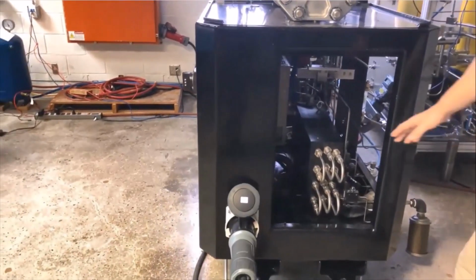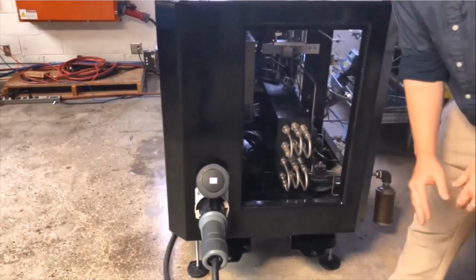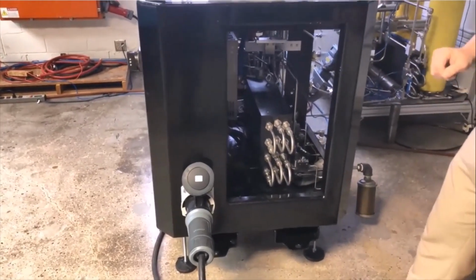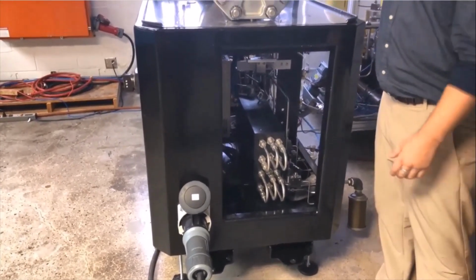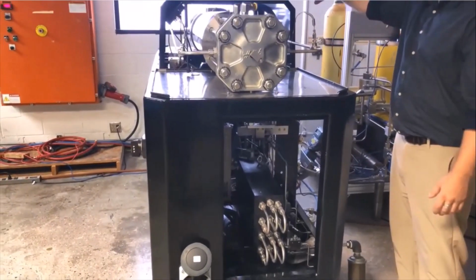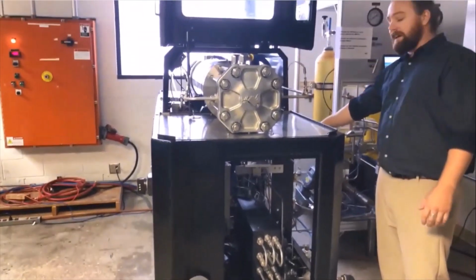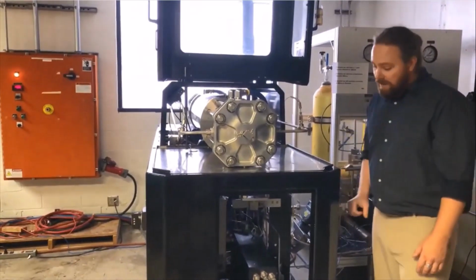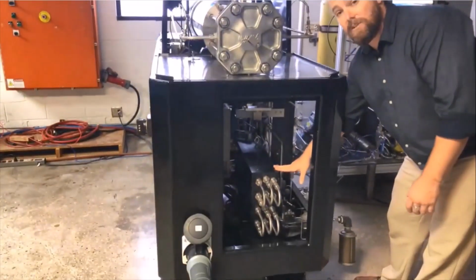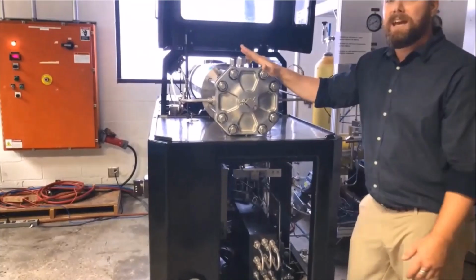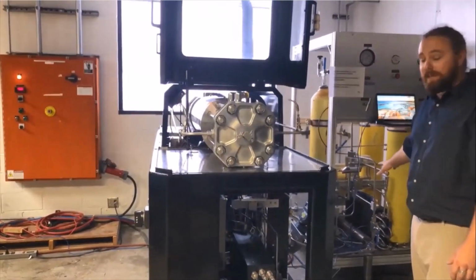This is the heat exchanger. We can use this as a pre-chiller. We can use it as an after chiller in a 2-stage configuration where we take the first stage and store it inside an interstage vessel. That gets cooled down by the heat exchanger as well before it enters your second stage and then downstream to your application.